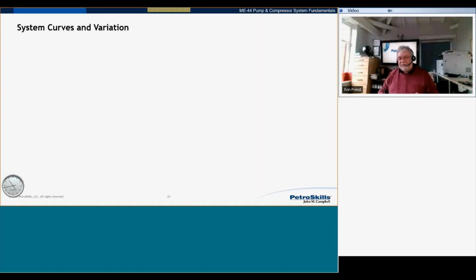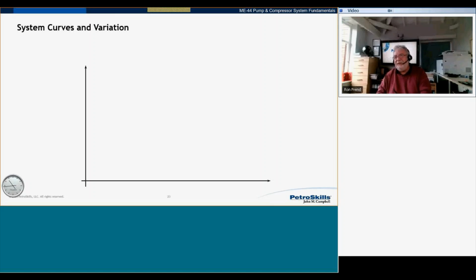Okay, so what we've done, we've calculated the friction head loss. We've calculated all the friction loss associated with those additional fittings. And now what we want to do is figure out what the actual operating point is. So that's easy. I'm going to use my head against flow curve to develop my system.